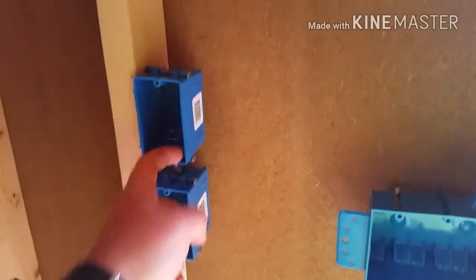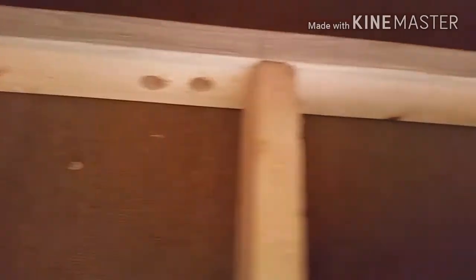Got all my boxes set up. I drilled a one-inch hole through each one of my two-by-fours and put this box up as a junction box, so I can bring power in here and split it off three ways with a wire nut and bring it into each one of my switches. Then I drilled two holes up there to run across the top to the plug-ins and one hole to go up and hit my ceiling fans.